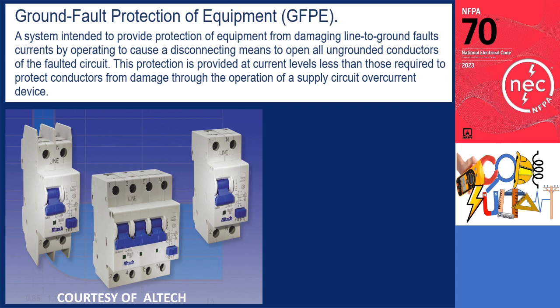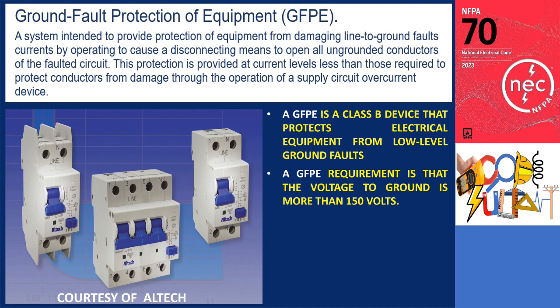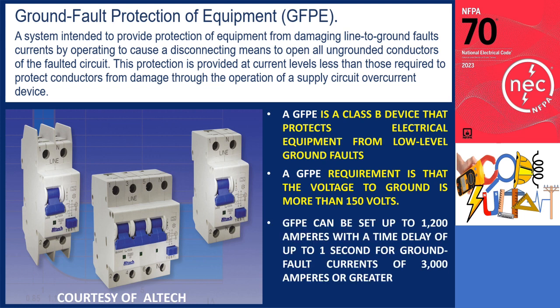Ground Fault Protection of Equipment (GFPE) is a system intended to provide protection of equipment from damaging line-to-ground fault currents by operating to cause a disconnecting means to open all ungrounded conductors of the faulted circuit. This protection is provided at current levels less than those required to protect conductors from damage through the operation of a supply circuit overcurrent device. A GFPE is a Class B device that protects electrical equipment from low-level ground faults but does not provide protection for personnel like a Class A GFCI device does. The GFPE requirement applies when the voltage to ground is more than 150 volts, which rules out the typical 120/208 volt system. In a 277/480 volt system, the voltage to ground is 277 volts. Furthermore, a GFPE can be set up to 1200 amperes with a time delay of up to one second for ground fault currents of 3000 amperes or greater, which would be lethal to a human being.